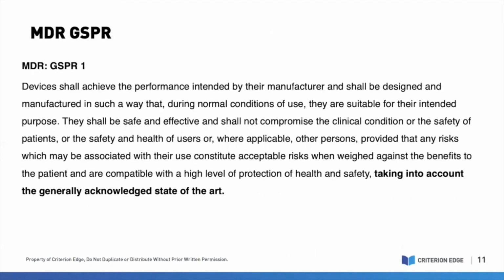For your reference, I've included here the text from GSPR1, which really underpins this whole discussion about endpoints, state-of-the-art endpoints, and acceptance criteria. This requirement has really been reinforced under MDR. The evaluation of the device must be performed within the context of the state-of-the-art, and specifically that there is an evaluation of the device's safety and performance objectives against quantitative acceptance criteria.